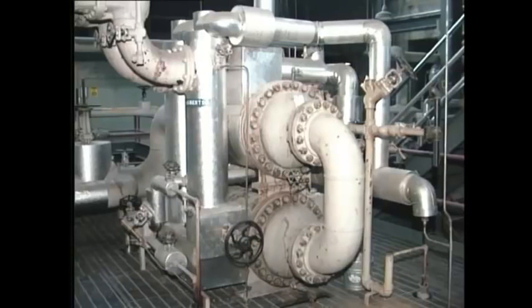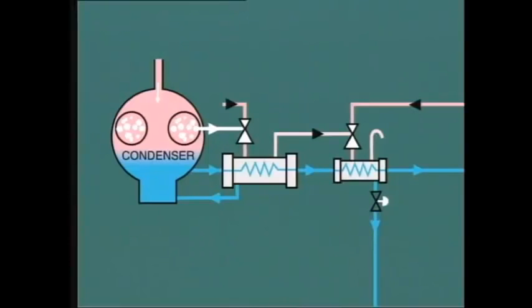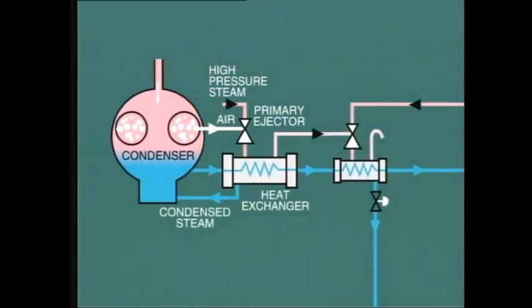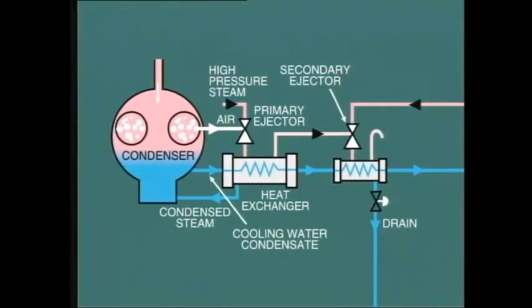However, the requirement for air removal when the turbine is in service is much less. Therefore, the on-load ejector uses smaller nozzles and has some heat and steam recovery. As before, air is drawn from the condenser by the primary ejector, and the air and steam mixture discharges into a heat exchanger to condense the steam. The cooling medium is usually condensate, so all of the heat is retained within the cycle from the intercooler. The air is now drawn into a second stage ejector, which is at quite low pressure, that is, a modest vacuum. From here, the air and a small amount of steam is exhausted to atmosphere.